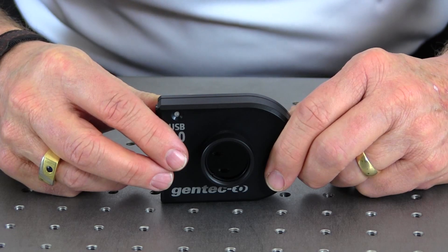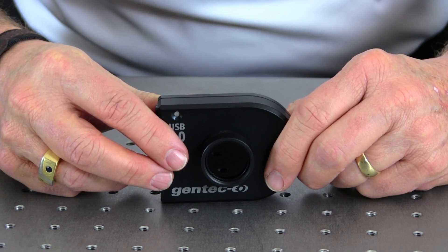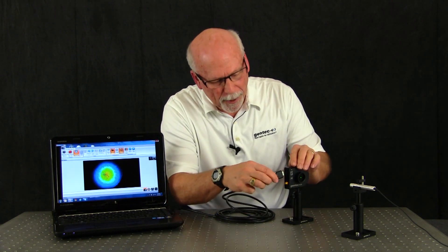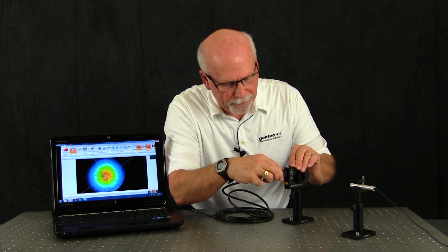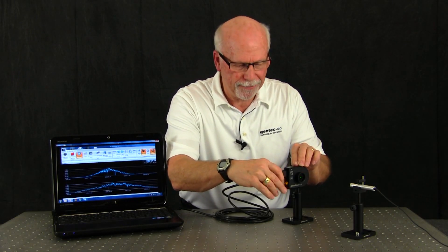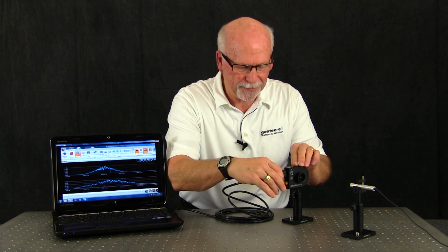Now, let's go ahead and make connections. I've already set up the beamage 4M camera with a low-power laser diode. First, let's plug the lockable end of the USB cable into the camera and make sure you secure it. Next, we'll plug the other end of the USB cable into the USB 3 port on our computer for maximum performance, though both of our cameras will work with the USB 2 connection. That's it. We're ready to bring up the beamage software.